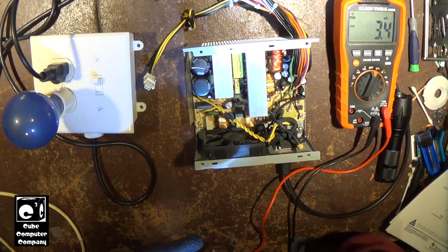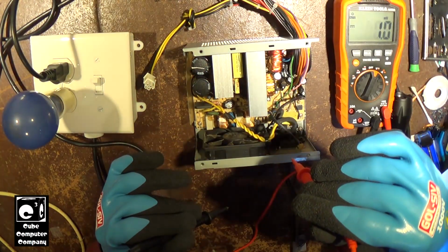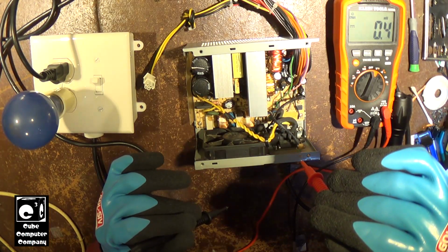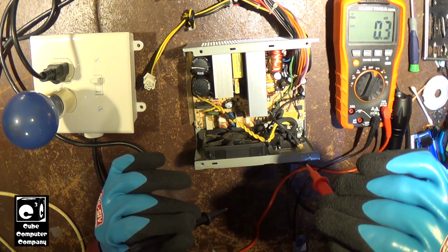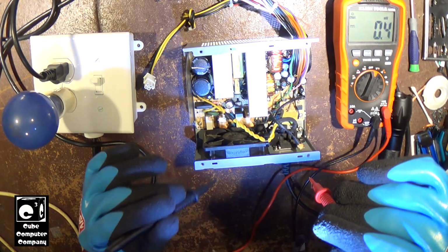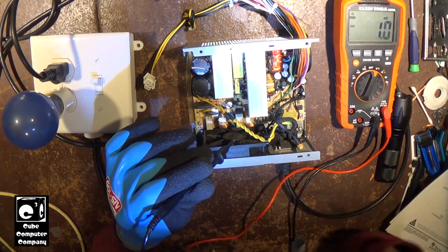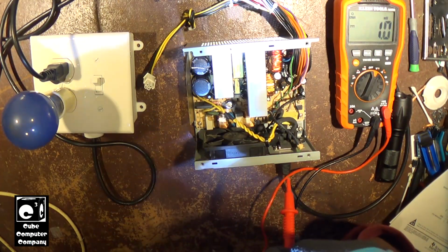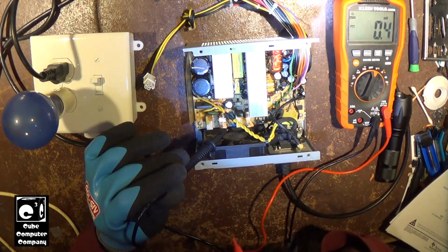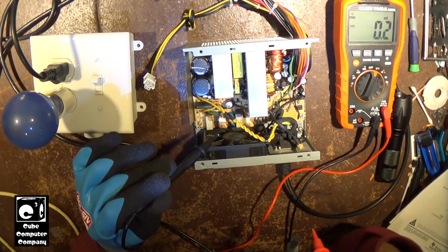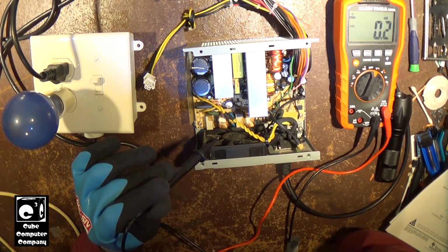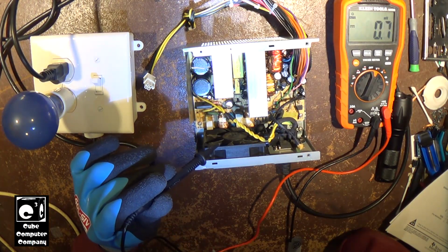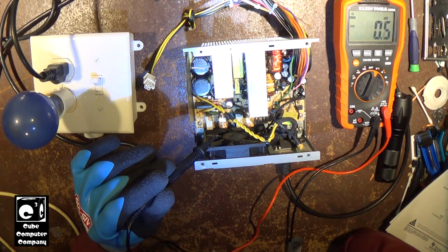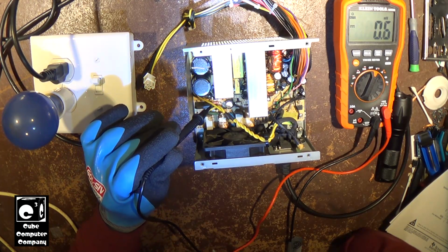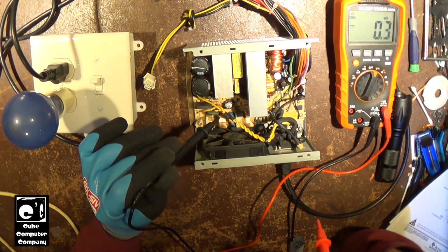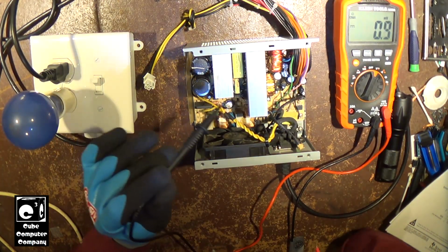What's going on with this unit is when the supervisor chip sends a signal on the FPO pin, which is active low, meaning it pulls to ground to light up the LED inside the optocoupler. What's going on is this optocoupler is defective or faulty. Because on the other side of the optocoupler you have a phototransistor, which is supposed to lower resistance down to basically nothing - it saturates and allows current to flow through it like a switch. That's not happening here, so this PWM chip isn't seeing this auxiliary 14 to 15 volts on its VCC pin, and therefore it's not powering up the power supply.